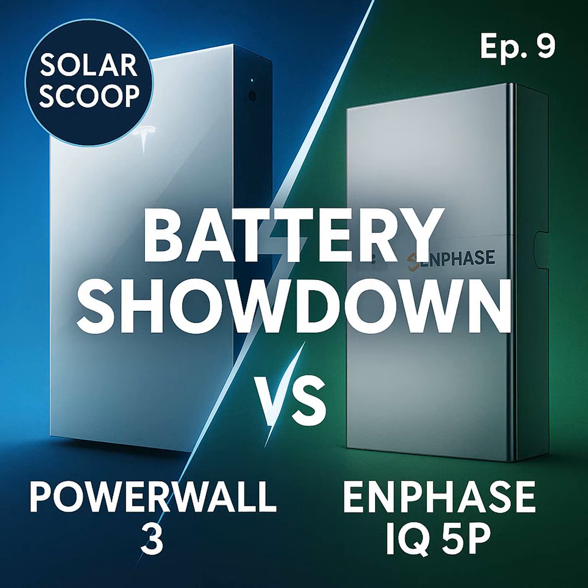And that starting power, the peak capability, is really something. It's rated at 185 LRA, locked rotor amps, that's the initial surge needed to get big motors spinning. That high LRA means it's less likely to stumble when you try to start up, say, your AC and the fridge kicks on at the same time during an outage. Makes sense, fewer tripped breakers when you least need it.